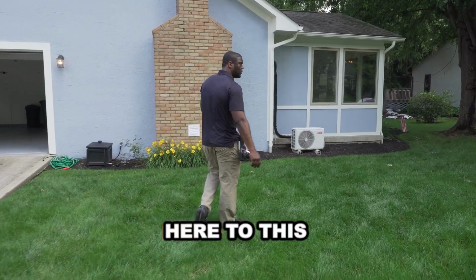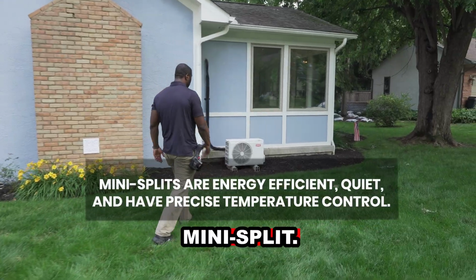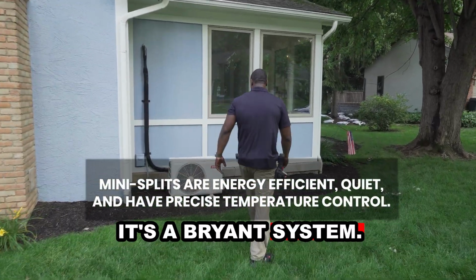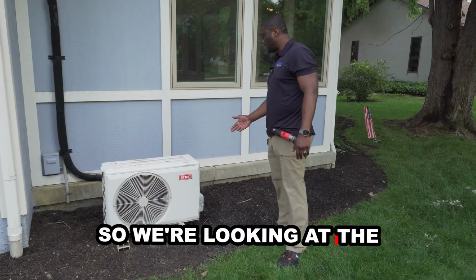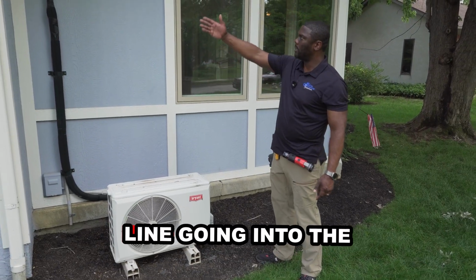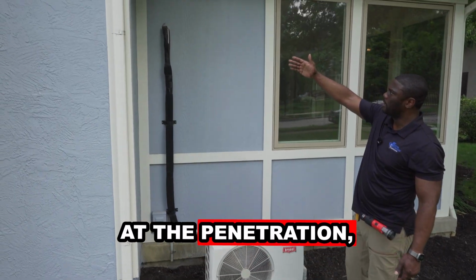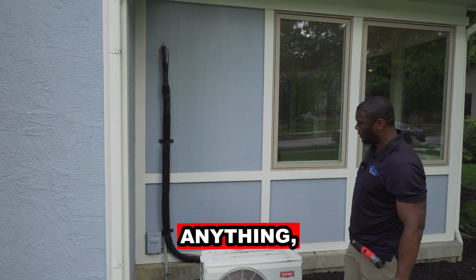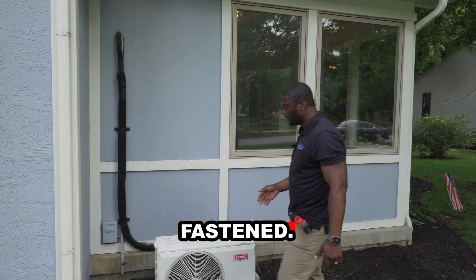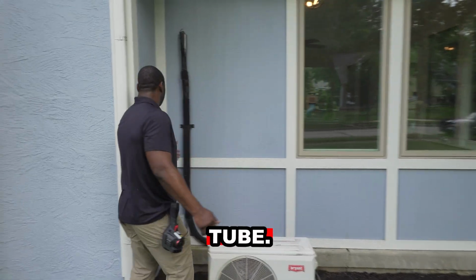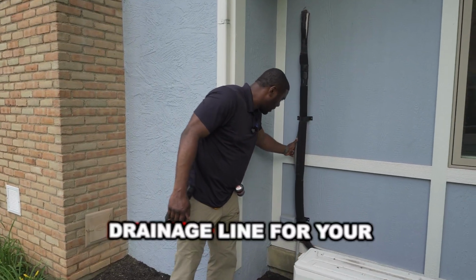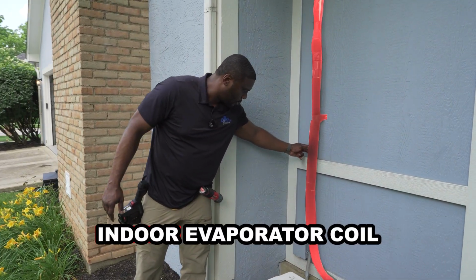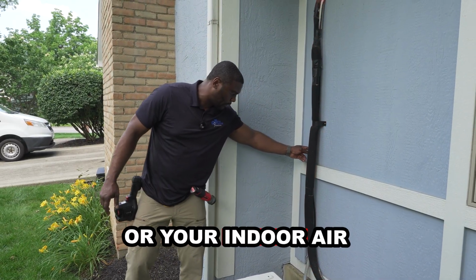So we're walking over here to this mini split. It's a Bryant system. So we're looking at the liquid line and suction line going into the house. We want to look at the penetration, make sure that there's no openings or anything. Look at how it's fastened. Here we have the drip tube. So this is your drainage line for your indoor evaporator coil or your indoor air handler.